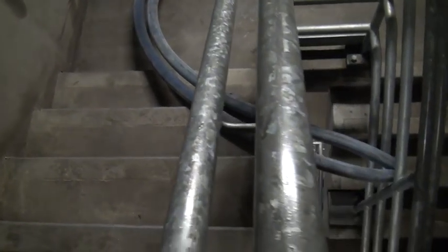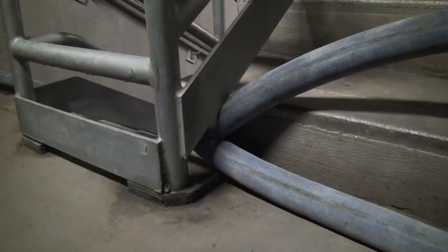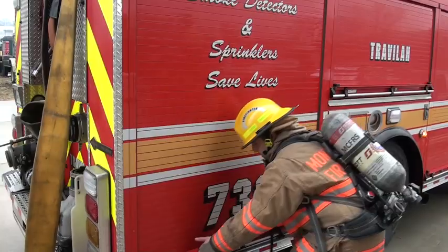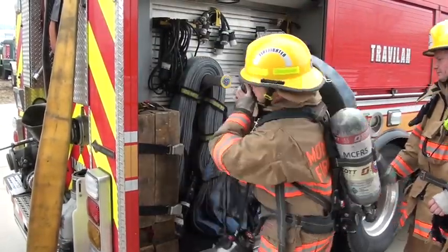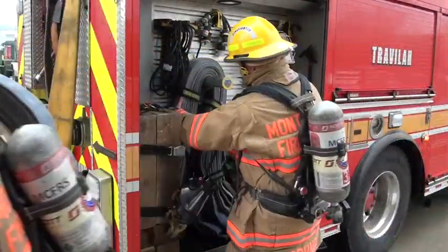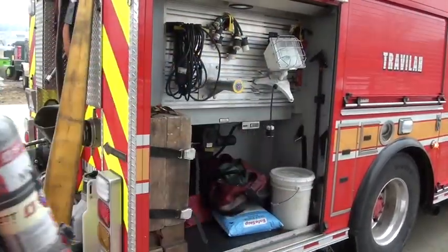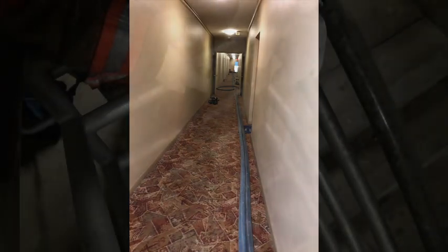When deploying a hose line in a stairwell, be sure the hose line is not under railings before charging. Though code permits a maximum of 200 feet between a riser and the furthest occupied living space, crews should be prepared to extend the hose line beyond that 200 feet. A minimum 200 feet of hose should be brought into a mid or high-rise building.